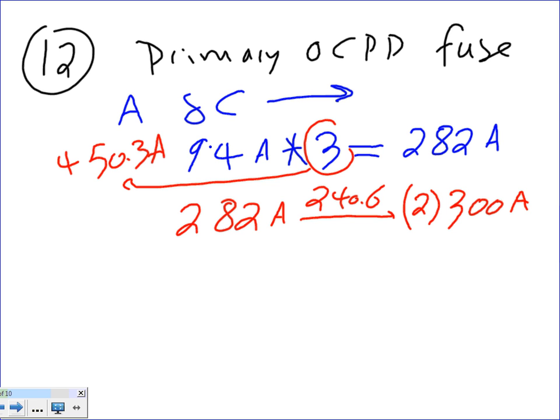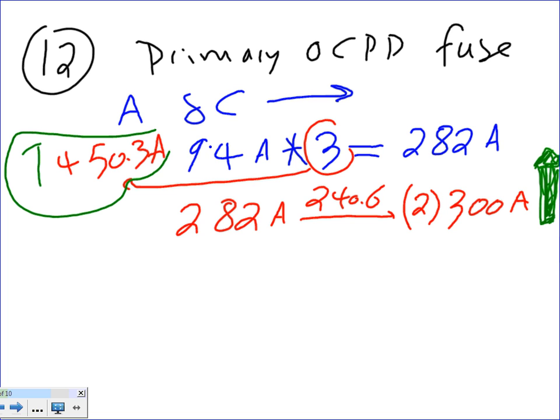Now I go up here. Why did I go up here, as we said yesterday? The ones who were here - I know a lot of you guys were not here because of the weather - but the ones who were here, we said there's a note number 1 under this table, 450. This is a table, an NEC table. If you go to this table, 450.3a, we went over yesterday. Under that icon there's note number 1, and it says if it's not a standard size, Spencer, what do you do? You go up. So I have 2 fuses, 300 amp.